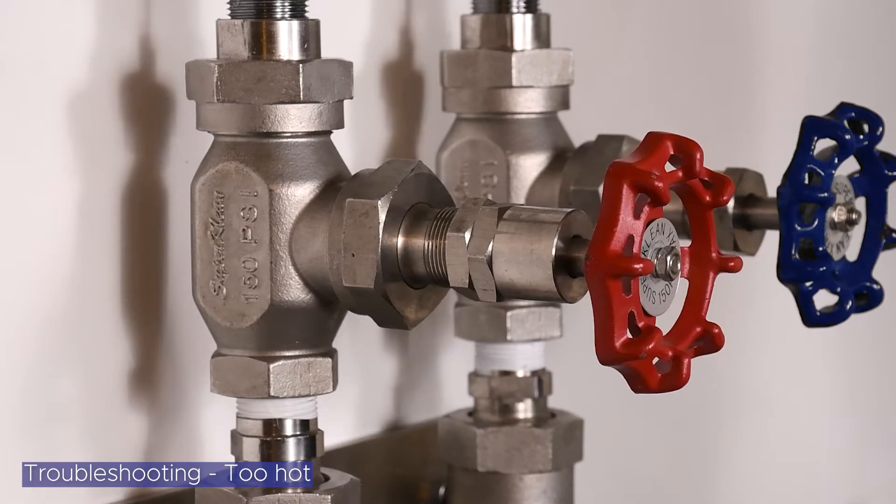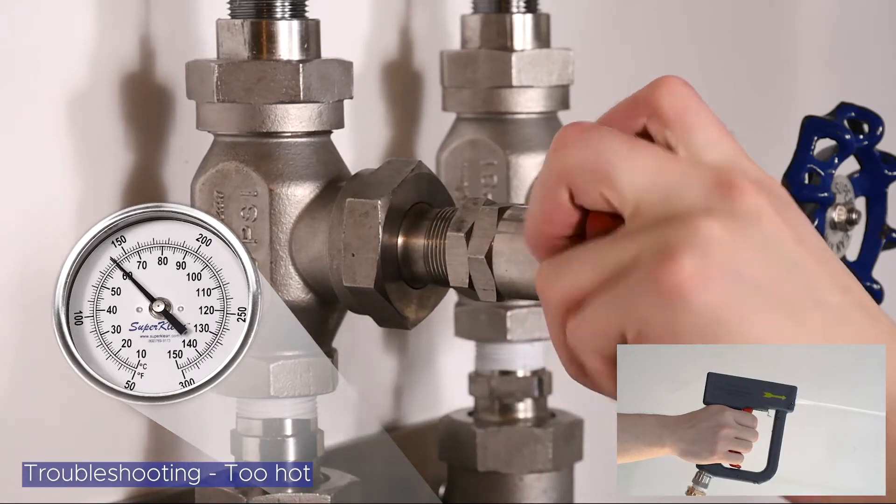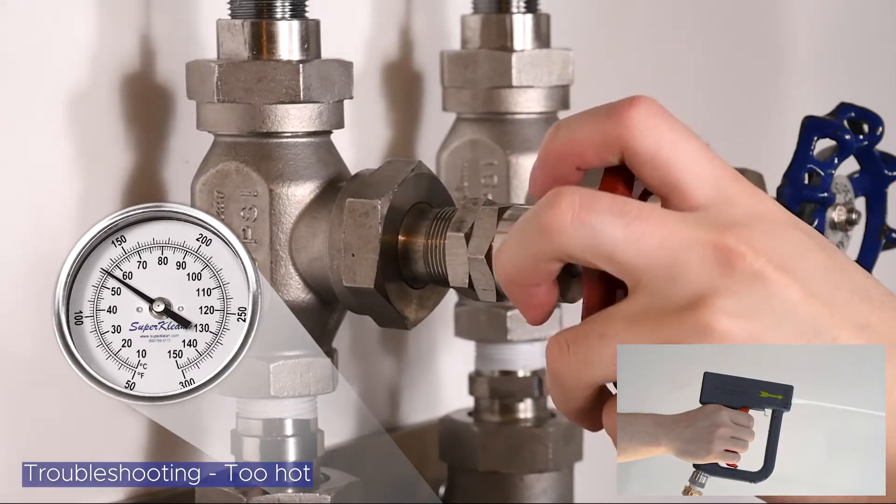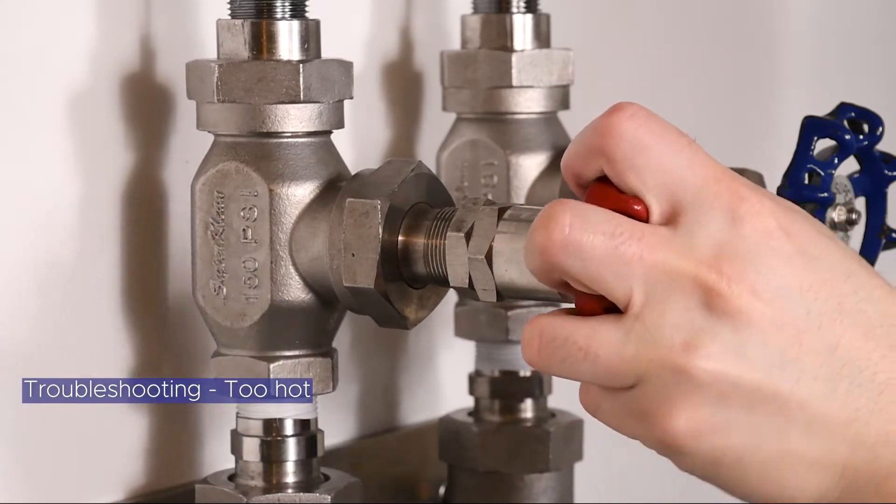If the water temperature output is still too hot after fully turning the temperature adjustment hand wheel counterclockwise, begin to decrease the steam flow by closing the steam globe valve by slowly turning clockwise while spraying the nozzle.